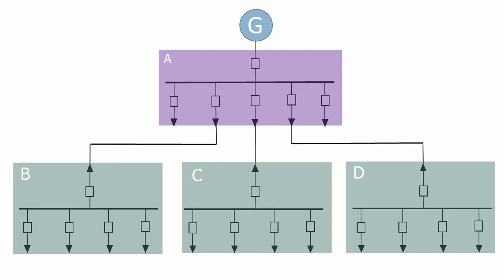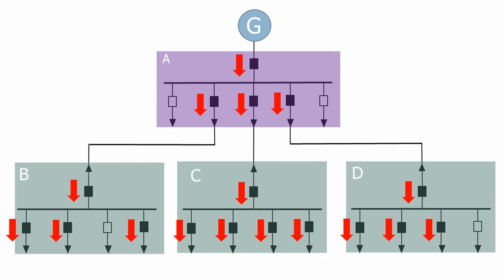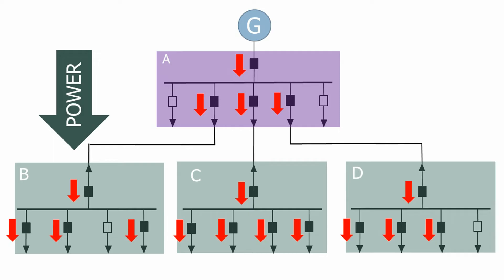Here we have a typical network with generators inside a power station at the top supplying power to the main feeder station, Substation A. This then feeds power to all of the other substations of the transmission network — Substations B, C, and D. Once the circuit breakers are closed, power flows from the generator through the main substation, through the feeders, and onto the individual substations which feed the loads. This is normally called a split system, as all the individual substations are fed separately from the main source of power.